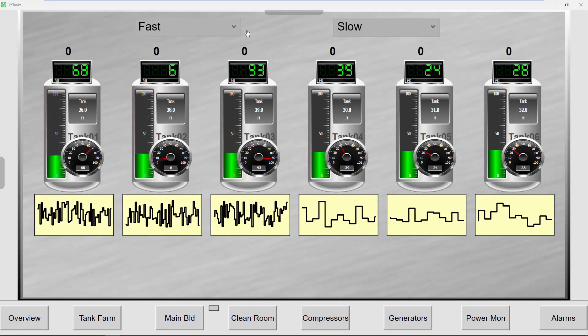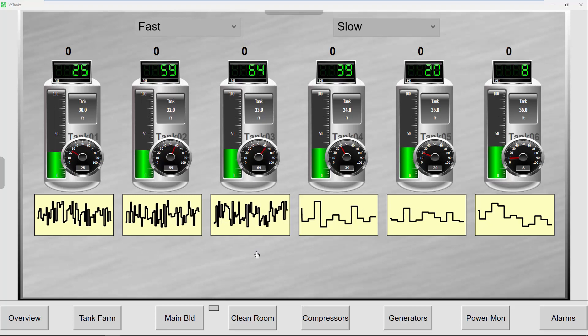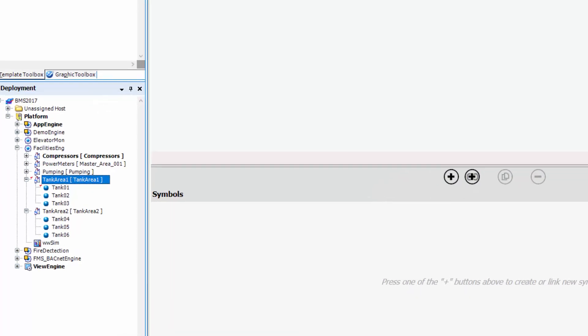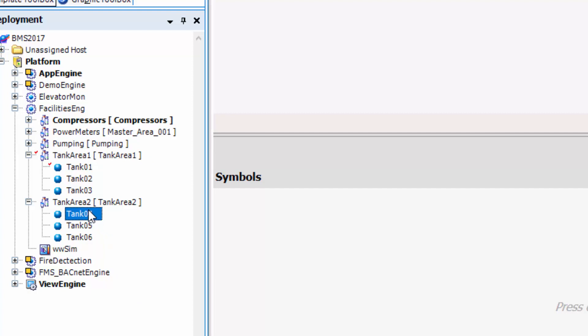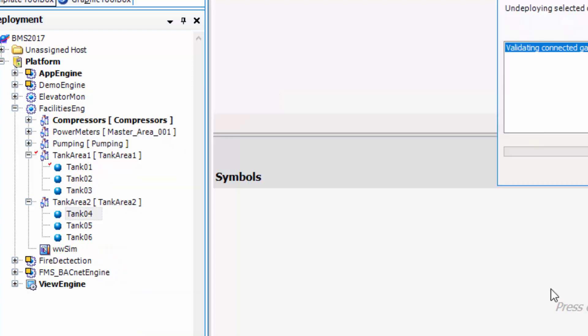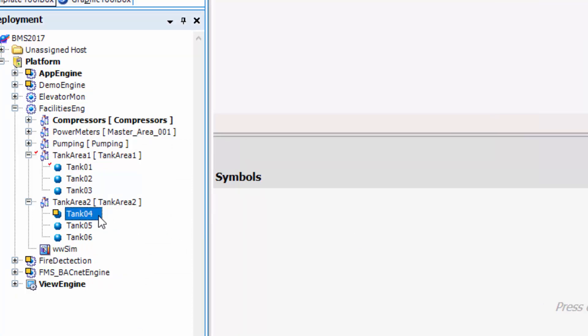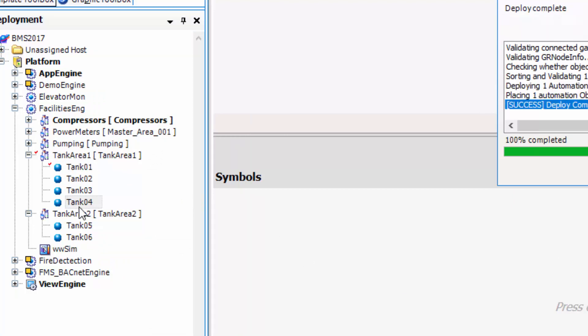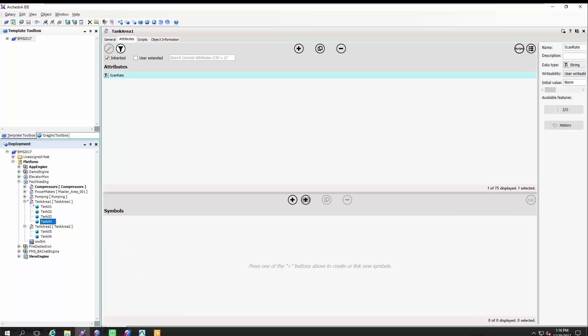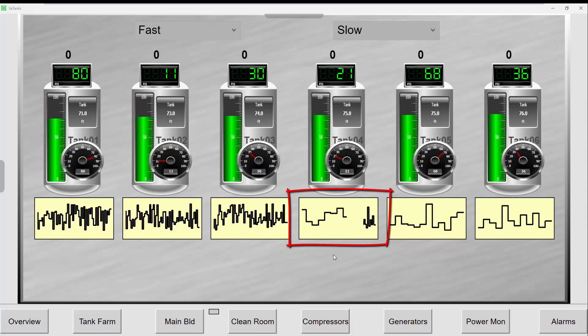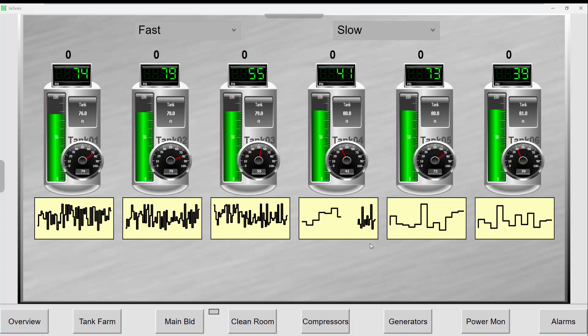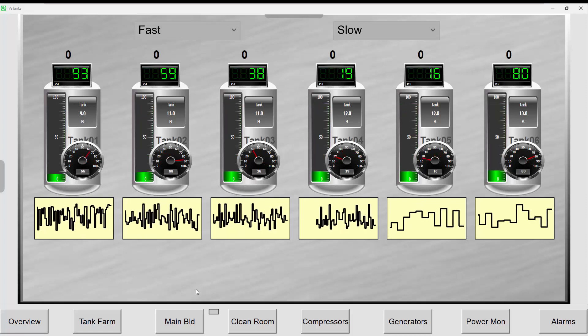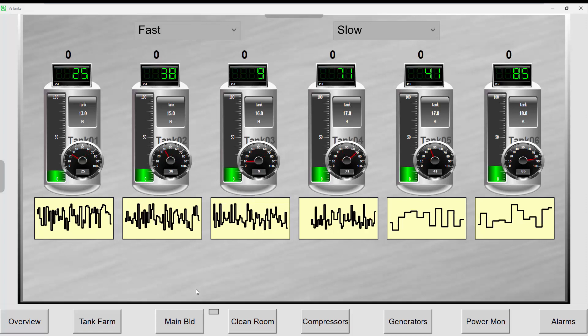Back in the HMI application, the first three tanks are set for fast scan rate and the last three for slow pull mode. If I want to change one tank and associate it with a different area, it's very easy inside Application Server using the 'my area' keyword in System Platform. I'm going to undeploy Tank Four, drop it into a different area - it's going to take on the personality of Tank Area One. After deploying it there, it will pull data from that specific area. You can see that just by dragging Tank Four into the different area, it starts pulling data much quicker because it's now associated with the fast pull rate for Tank Area One.